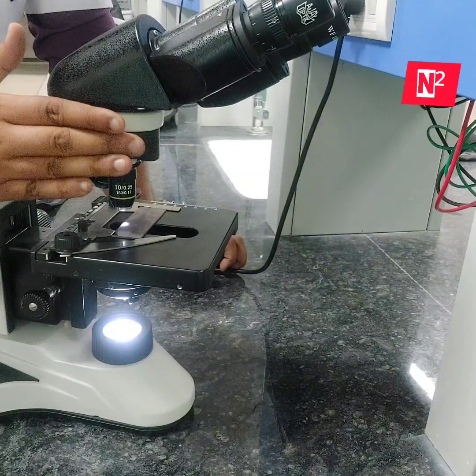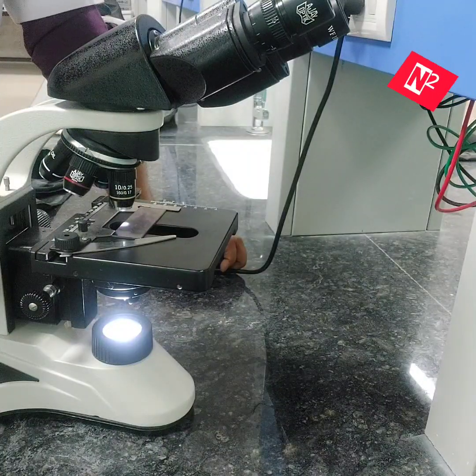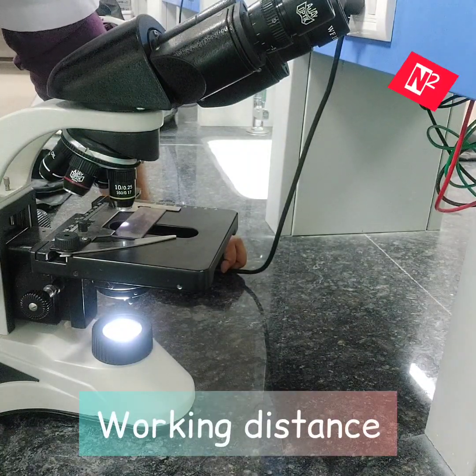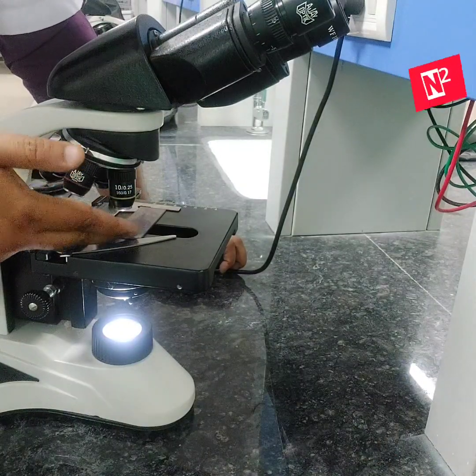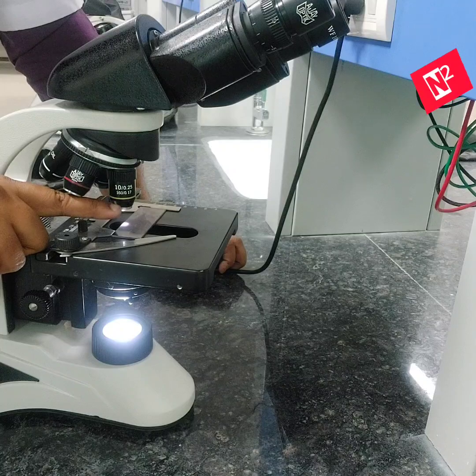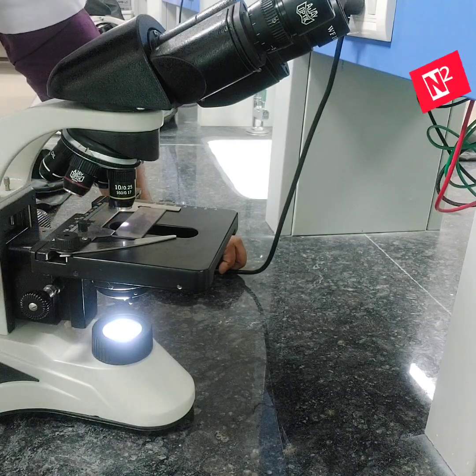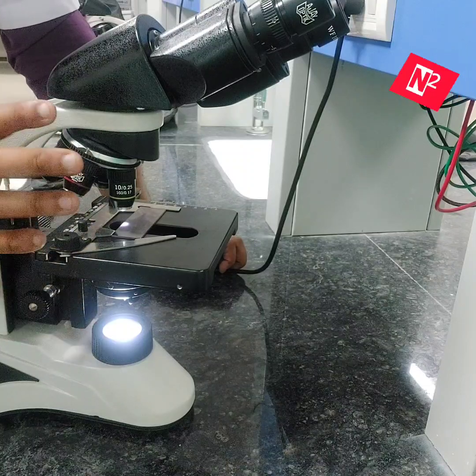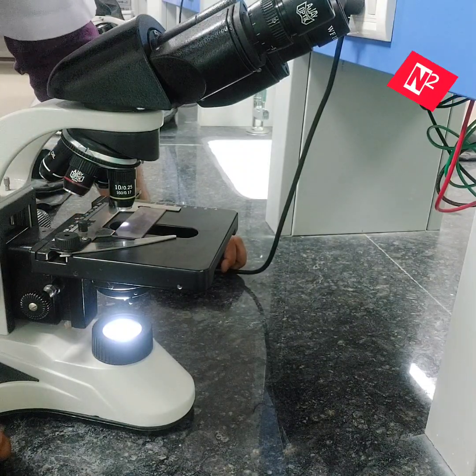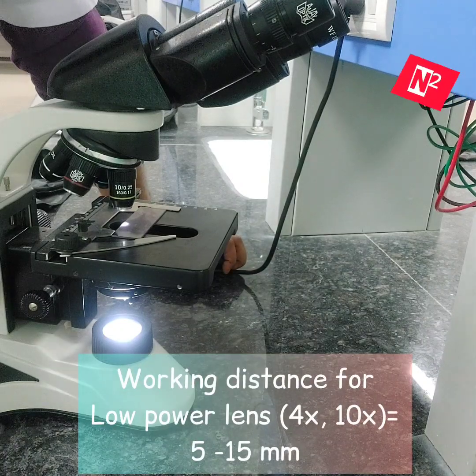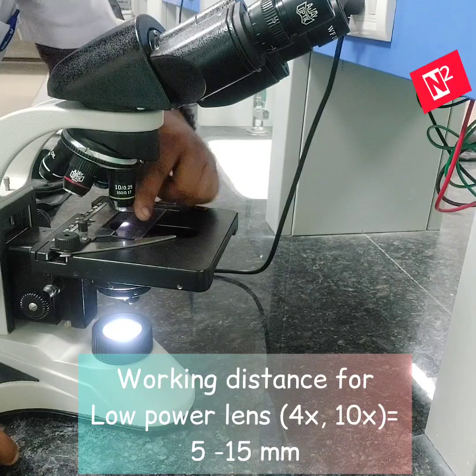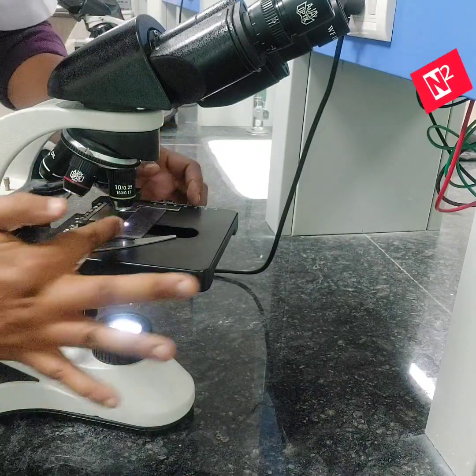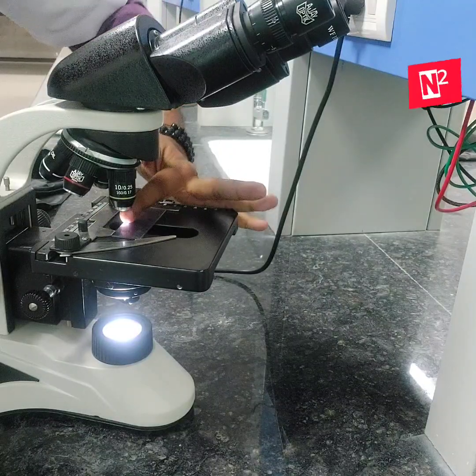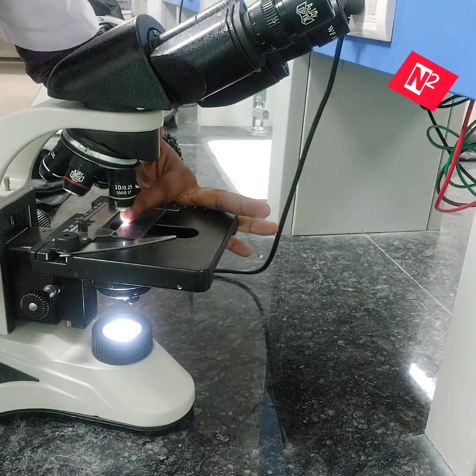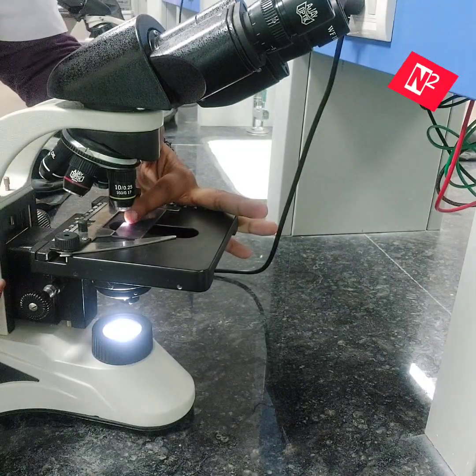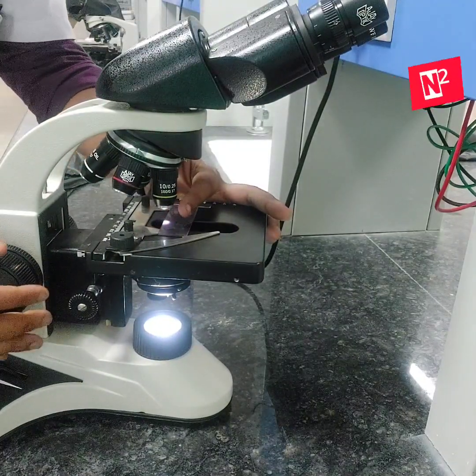Now this is the point at which you should know the principle of working distance. The working distance is the distance between the glass slide and the tip of the objective lens. For every power of objective lens, there is an approximate working distance to keep in mind. In case of the low power objective lens, the working distance should be 5 millimeter to 15 millimeter. That means it could be like the thickness of your finger. The gap between the glass slide and the tip of the objective should be like this. You might have to do some adjustment with the fine and the coarse adjustment screw to bring it into focus.